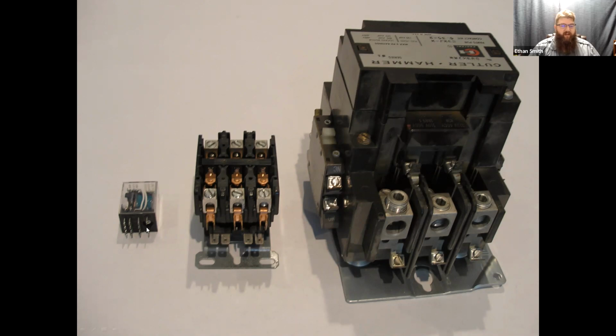On this one, they're back here. And on this one, they're actually in the middle right here. So those are our coil contactors. We may have different voltages. This is a 24 volt coil. This is a 24 volt coil. We can see on this one, it's actually a 110 volt coil. So it kind of depends on your application, but all they really are, guys, is big magnetically driven switches. That's what a contactor is. That's what a relay is.